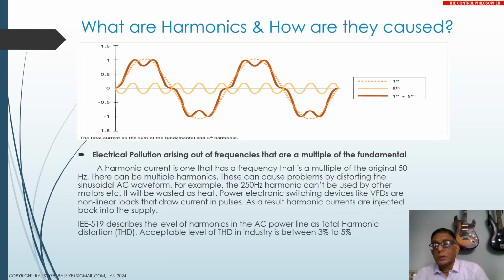Now, what are harmonics? See, harmonics are multiples of the fundamental. That is, suppose the drive is rated at 50 hertz: 100 hertz, 150 hertz, 200 hertz, 250 hertz. These are the multiples, or harmonics, of the fundamental 50 hertz. Now, this is a kind of electrical pollution. That is a corruption of the quality of power that is delivered to motors, and this also travels upstream. That is, it causes interference in the power supply of the drive itself. Okay. Now, why is this happening?